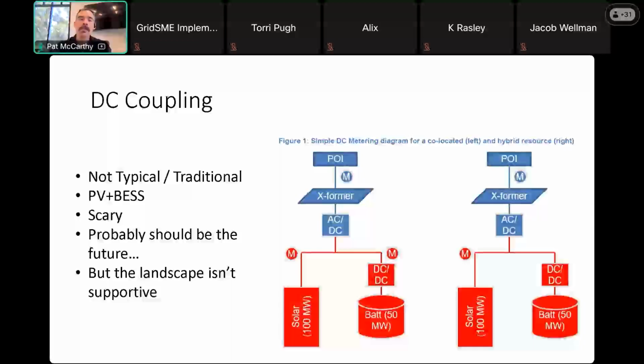When it comes to DC metering, CAISO is going to tell you that you still need a DC meter on every solar input to meet that VER requirement. And from a revenue metering perspective, you need analogous measurements between the solar and the BESS in order to separate them out appropriately. So you need a meter on the same side of the DC to DC converter as the PV, as shown on CAISO's drawing here on the left-hand diagram.